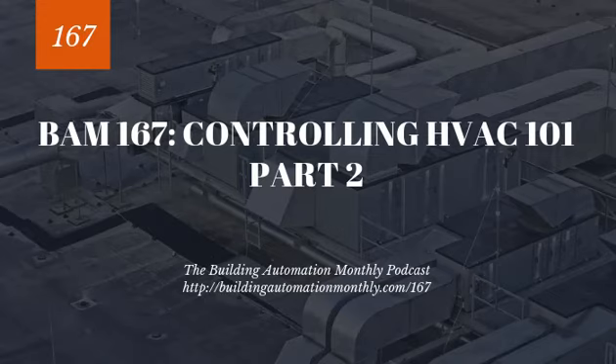Temperature, humidity, and CO2. Now, when we're looking at these systems that control the airflow, we're looking at systems that are often called rooftop units or air handlers. Now, a rooftop unit is typically known as a package unit. It's a self-contained unit, so everything within it is contained within itself. DX coils, gas heat.